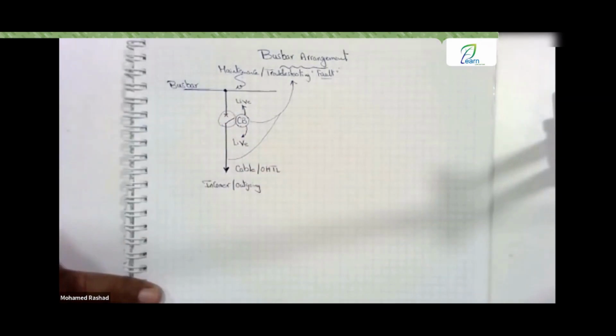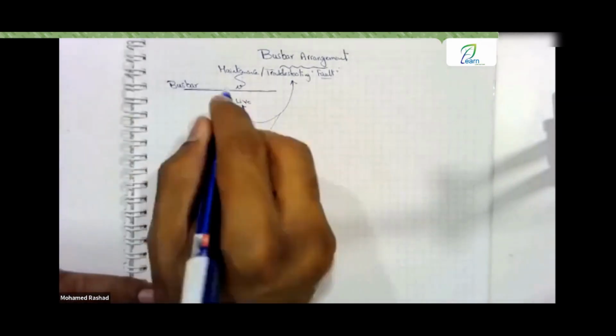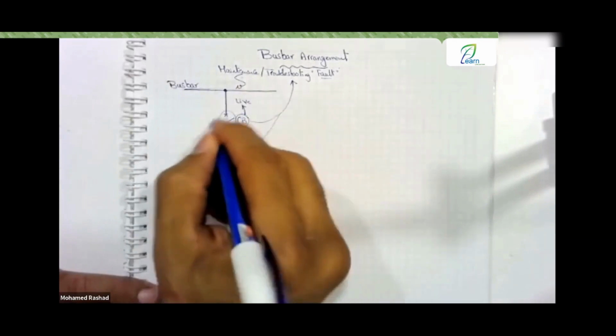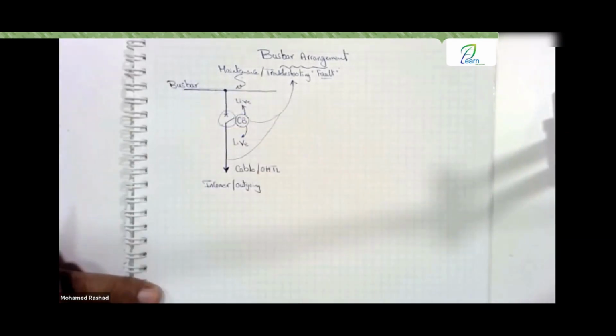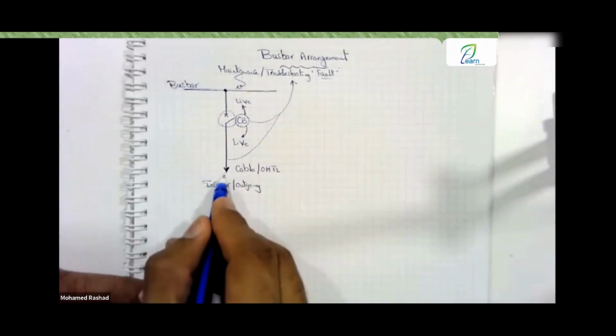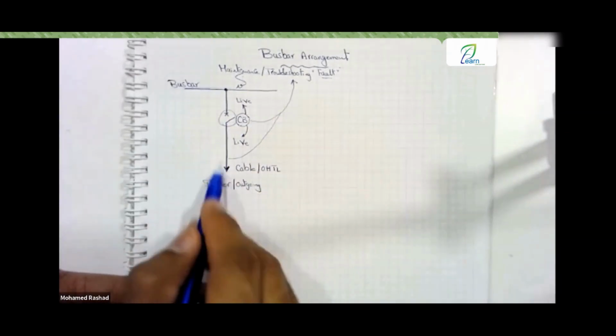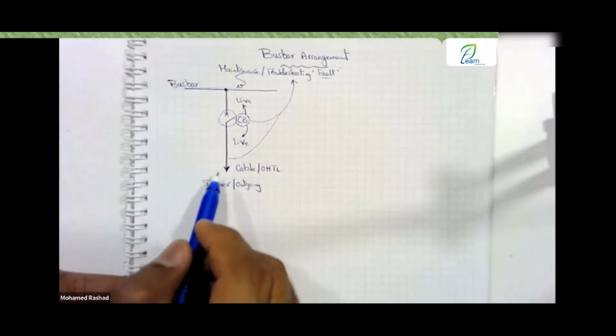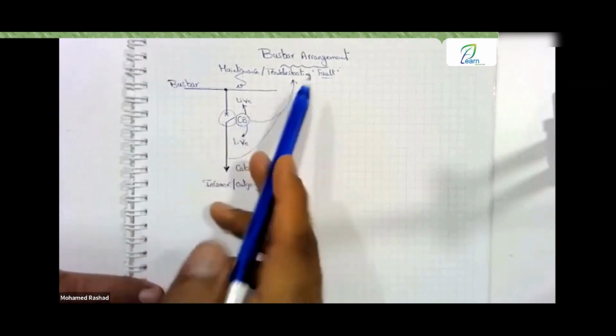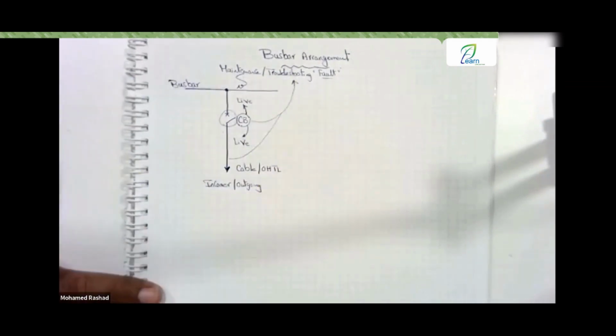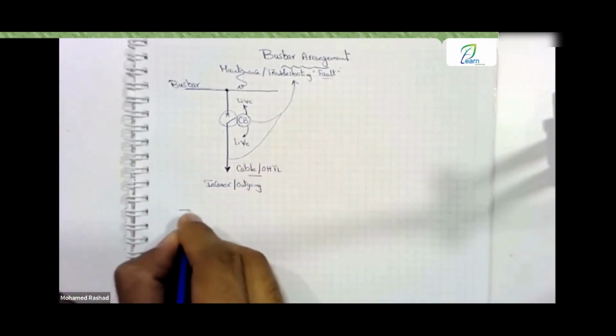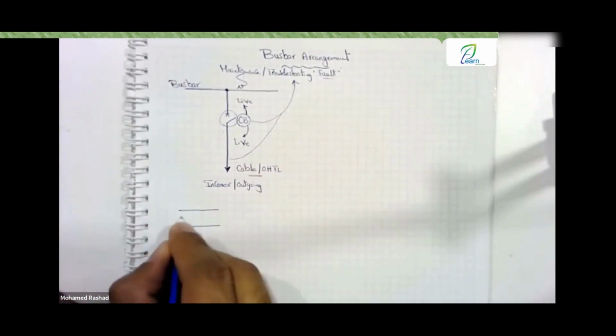Therefore, what needs to happen is you must disconnect both sides. You can never work on the breaker and the bus bar while it's live, nor can you work on this while the feeder you have is live. The last thing, your cable or load here, if you want to do the isolation here, it still gets voltage and you're troubleshooting in both cases. This cable of yours is the same idea. What is the cable essentially?